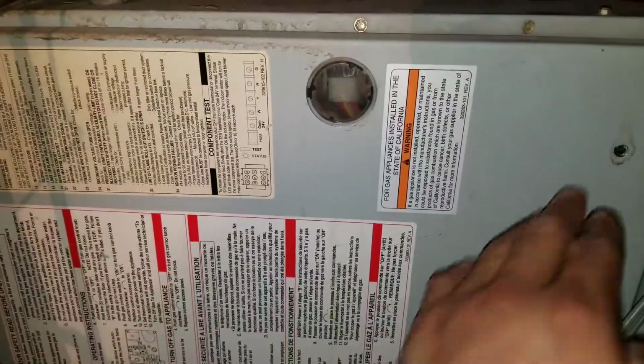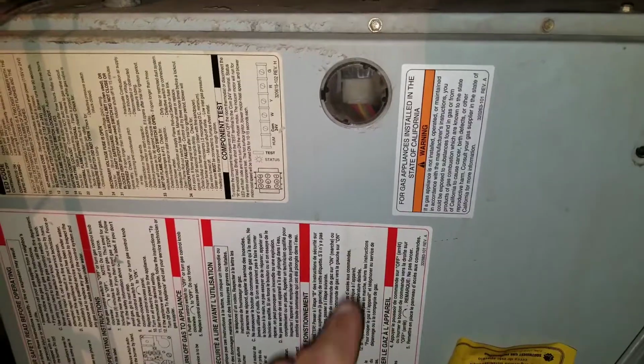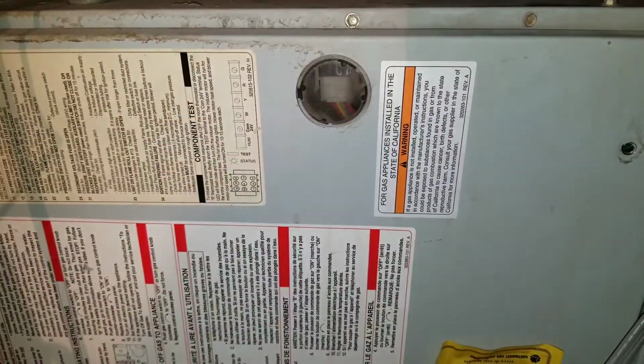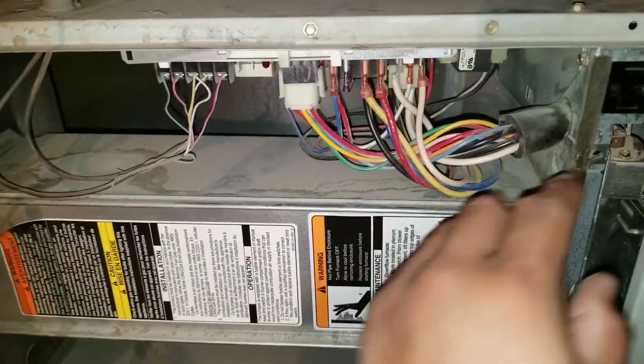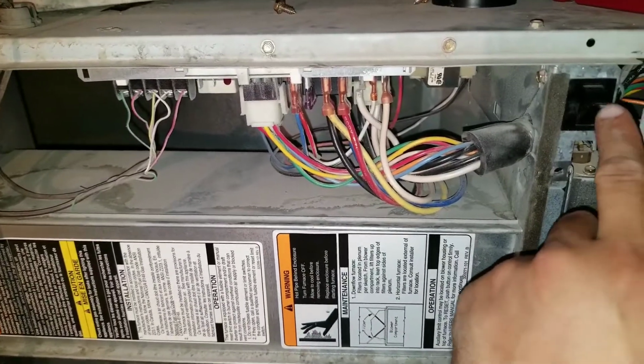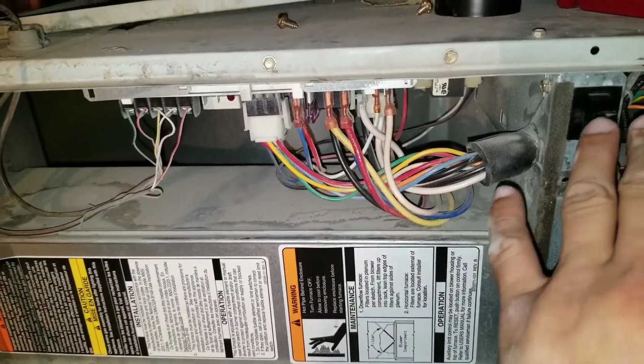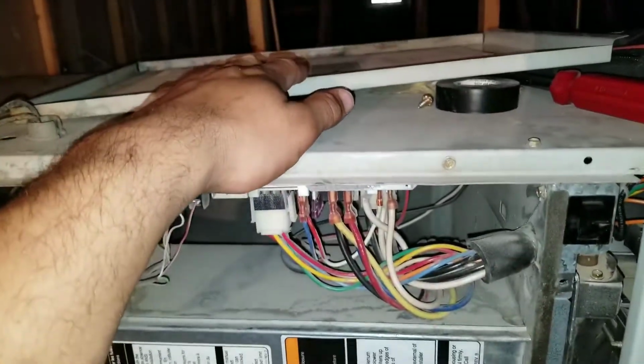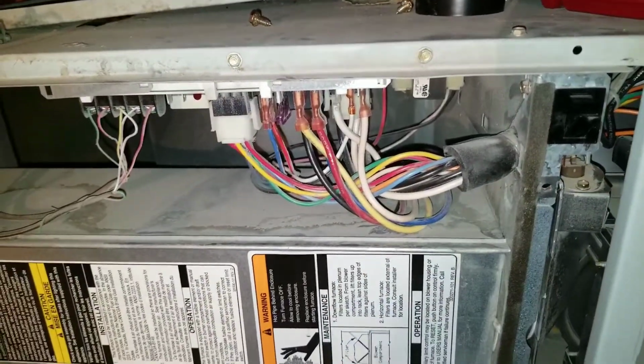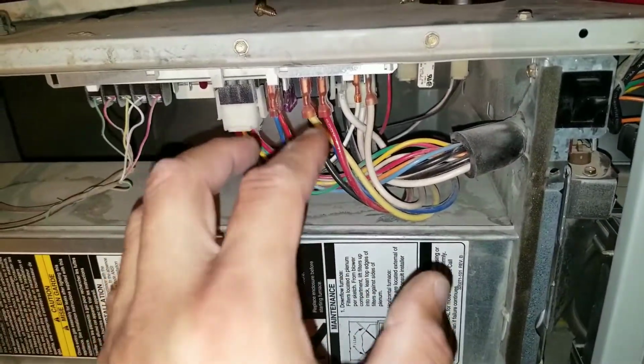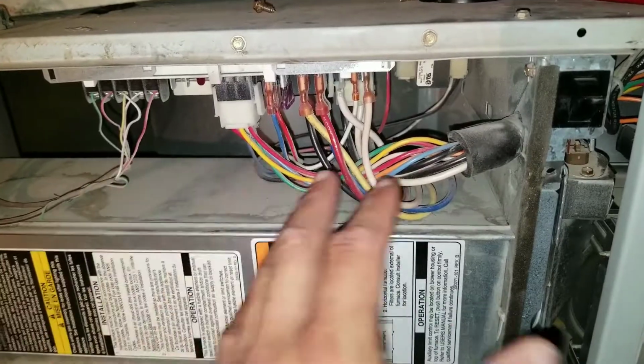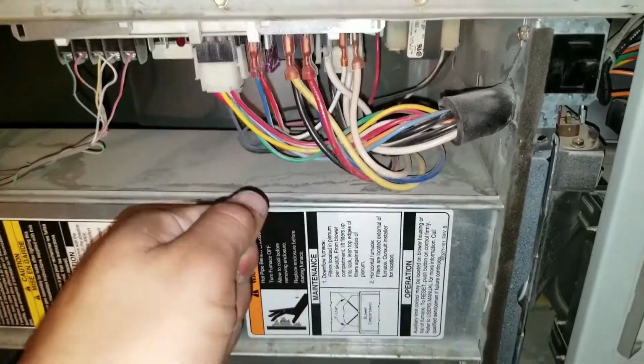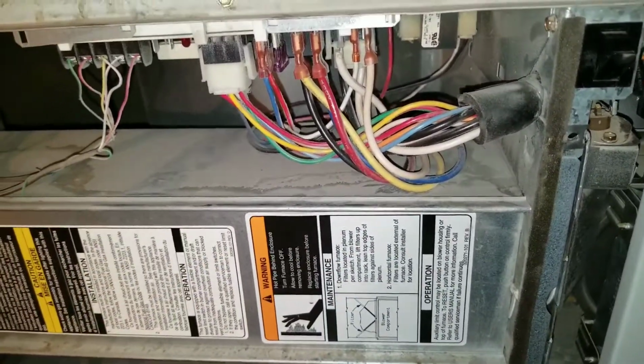So here I'm going to remove this panel so that I can get access to the board. Once you remove this panel, you're going to have to manually engage this switch. This will bypass the actual panel that's on here, and this will allow you to see and troubleshoot the board so that you won't have any restrictions when you're putting your multimeter probe and working on it.